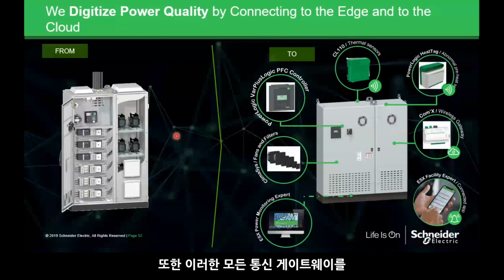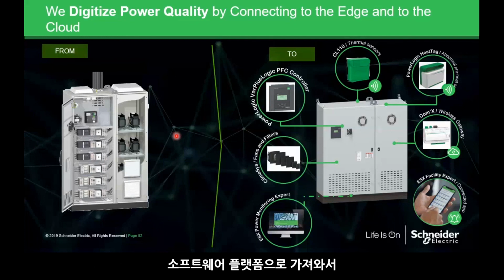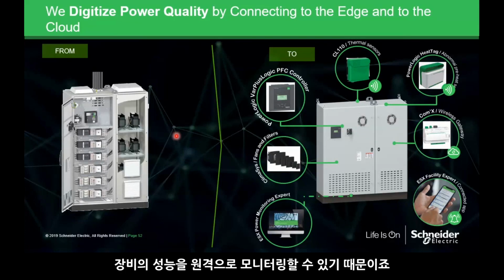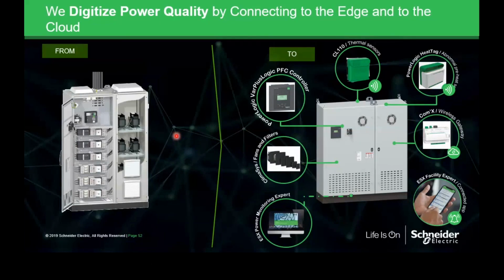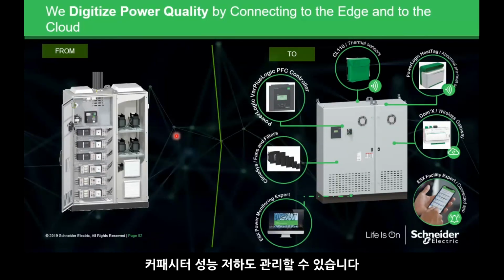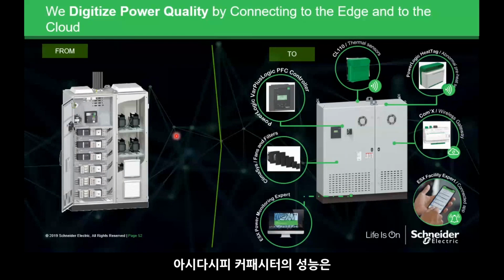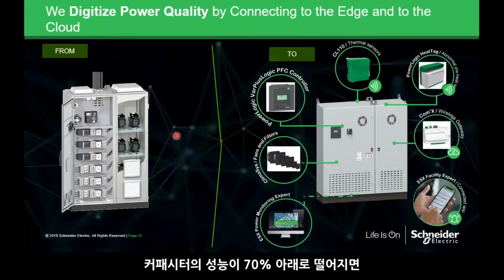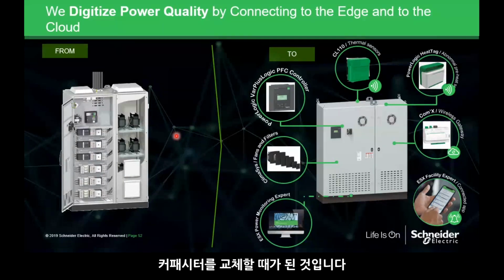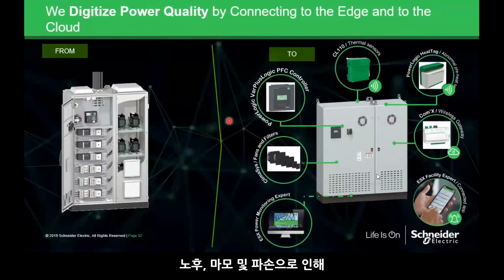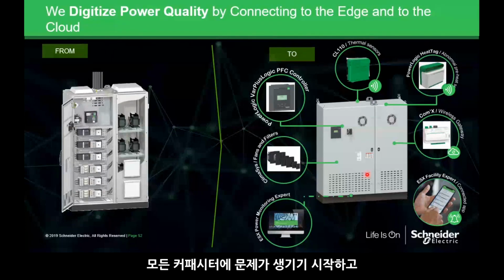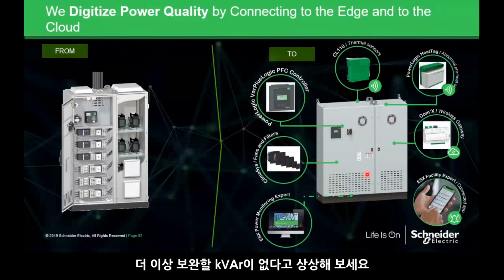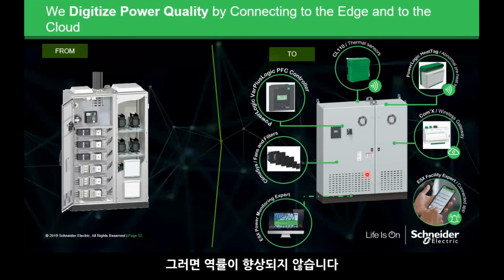So we have all these precautions in terms of safety. Then of course we also start to put communication gateways into the cubicle. Why? Because we are bringing all this information to the cloud or to a software platform where we remotely monitor the performance of the equipment. At the same time, we can also measure the derating of the capacitors. Capacitors over time will start to derate. Once you go below 70% of the capacitance, it's time to change the capacitor. Because of derating, aging, wear and tear, things start to fail. If all the capacitors fail, there is no kVAR to compensate anymore, the power factor will not improve, and you will keep getting penalties from the utilities.